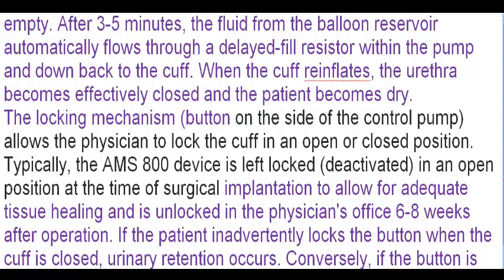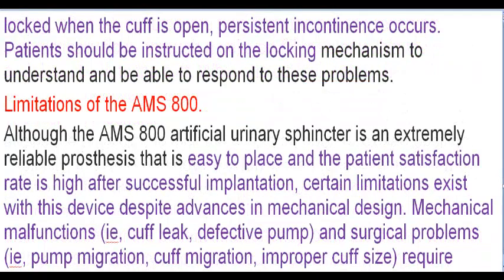The locking mechanism, a button on the side of the control pump, allows the physician to lock the cuff in an open or closed position. Typically, the AMS 800 device is left locked, deactivated, in an open position at the time of surgical implantation to allow for adequate tissue healing and is unlocked in the physician's office 6 to 8 weeks after operation. If the patient inadvertently locks the button when the cuff is closed, urinary retention occurs. Conversely, if the button is locked when the cuff is open, persistent incontinence occurs. Patients should be instructed on the locking mechanism to understand and be able to respond to these problems.